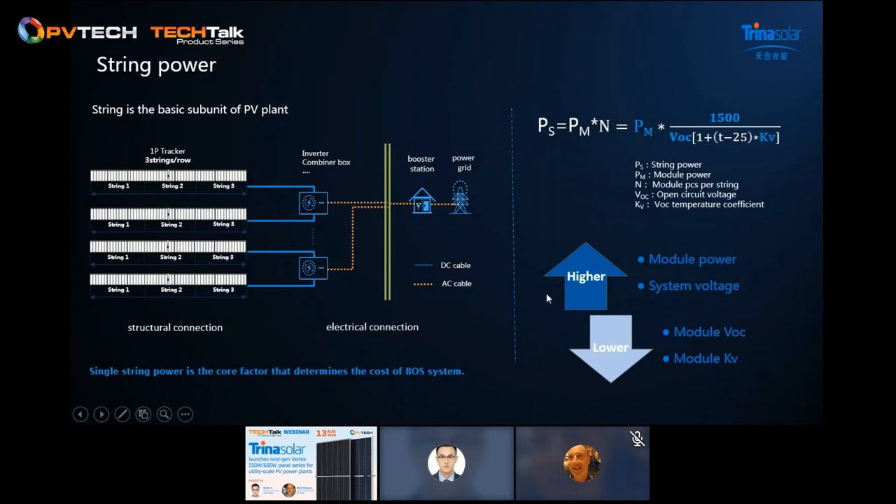How do we improve string power? PS (single string power) equals PM (single module power) times N (module quantities per string), which is determined by the system voltage and the open circuit voltage calibrated by the temperature coefficient. There are four ways to increase string power — two improvements and two reductions. Previously, all players focused on module power increase to increase string power without paying attention to voltage. This time, our new Vertex modules with low voltage design can significantly increase string power.